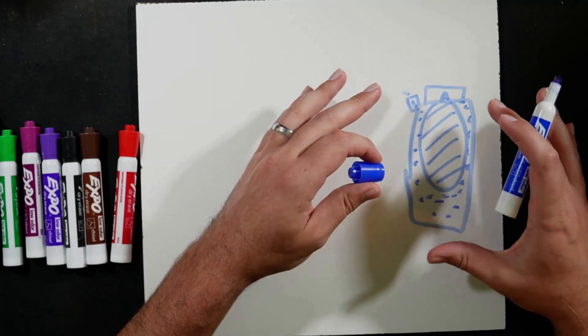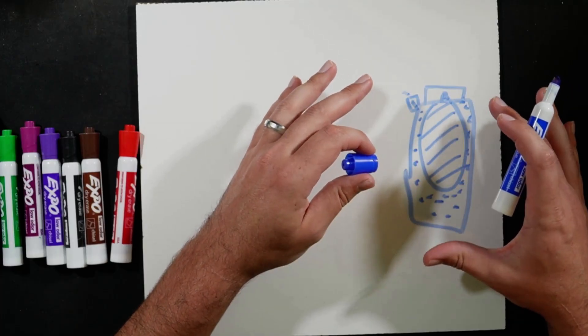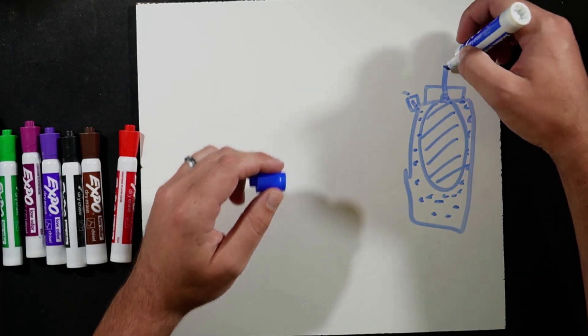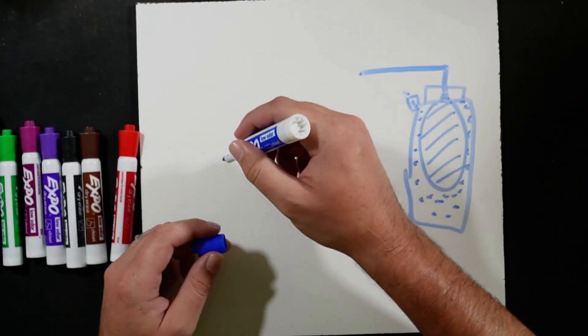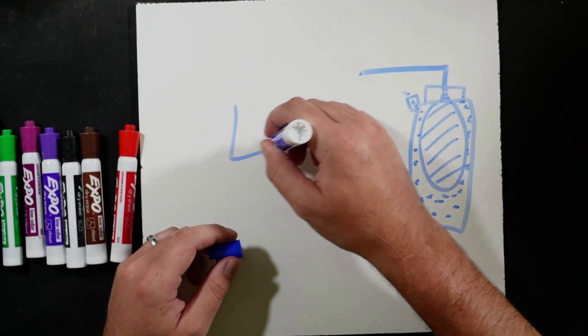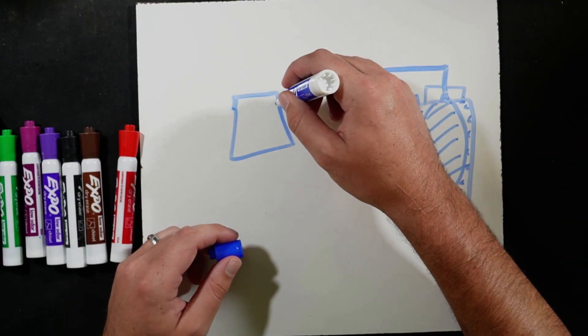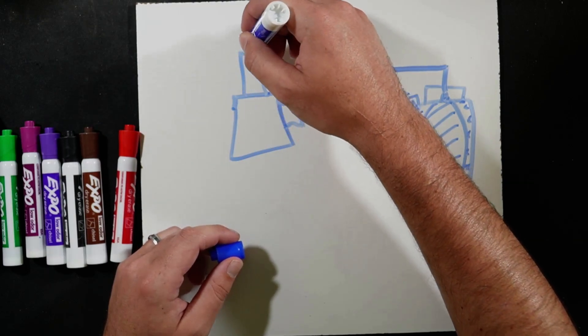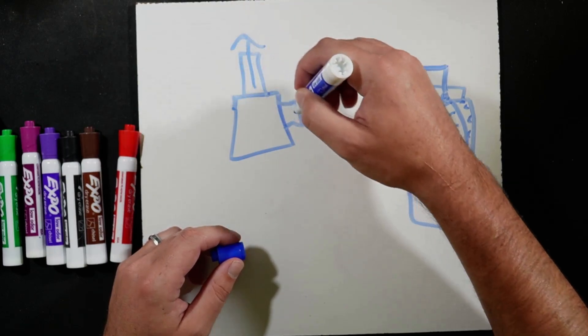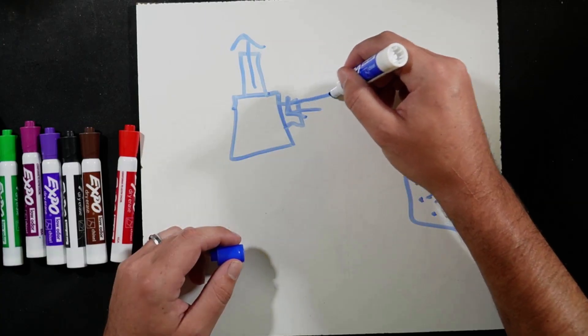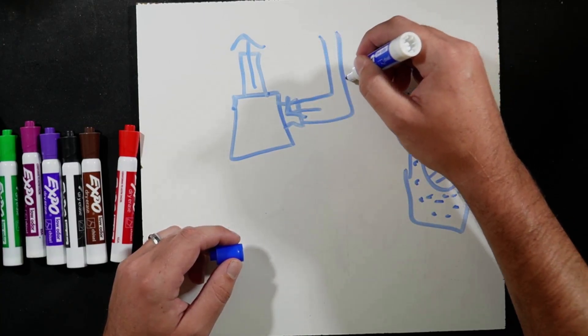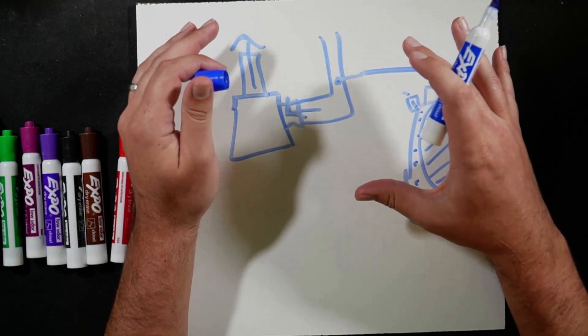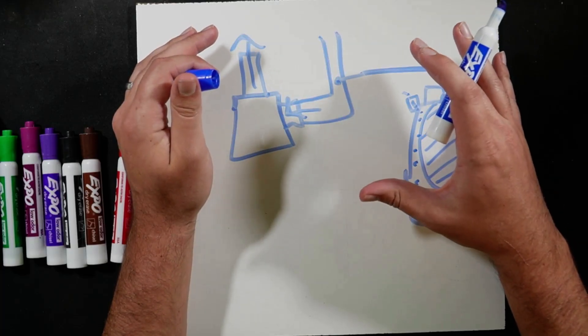The whole point of this system is to help us maintain water pressure on the loop. Specifically, we'll have a pipe coming over. If we have our pump assembly over here, this is the pump inlet flange and our outlet flange. We would end up connecting to this pipe here on the pump. This is the same place you would also have your makeup water connected as well.